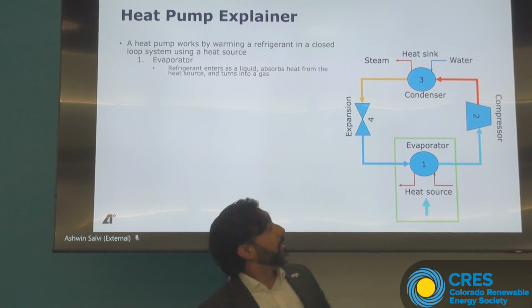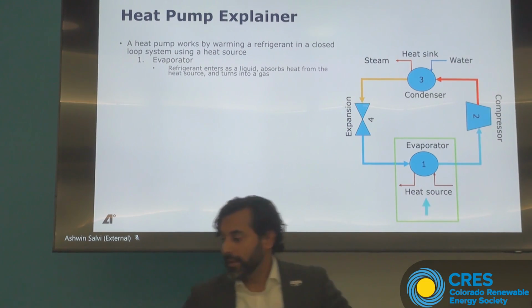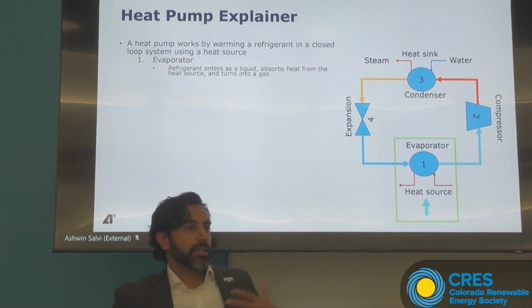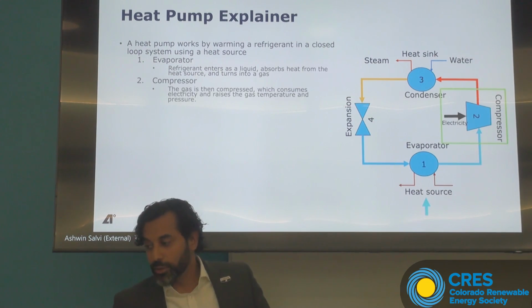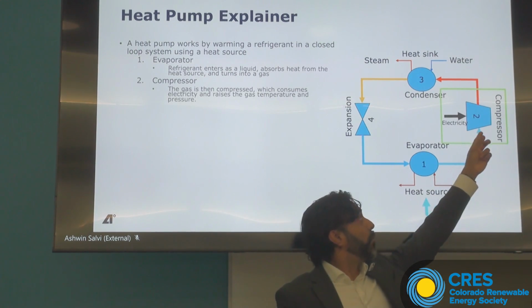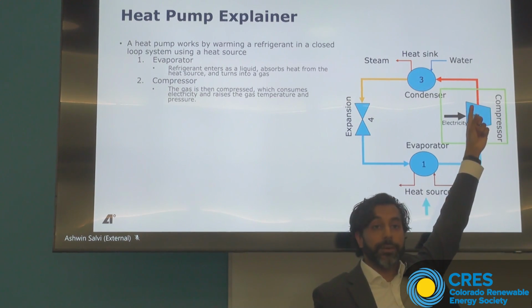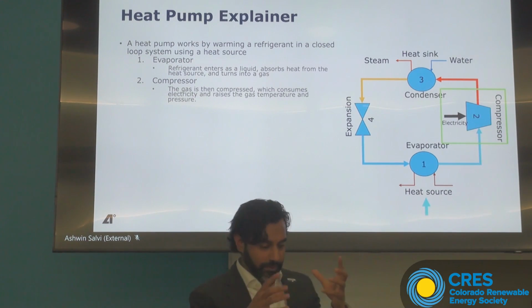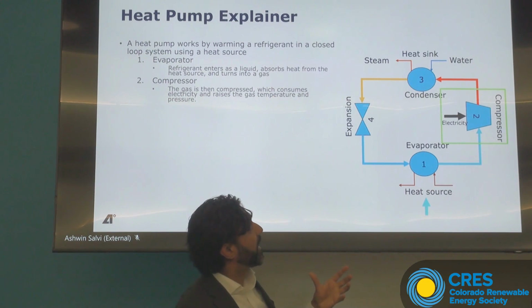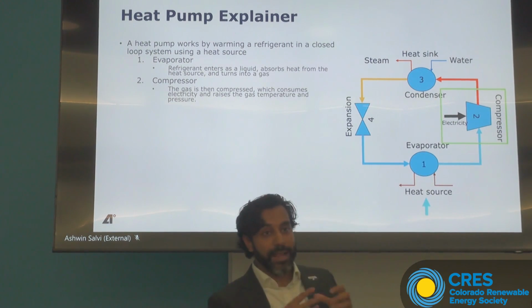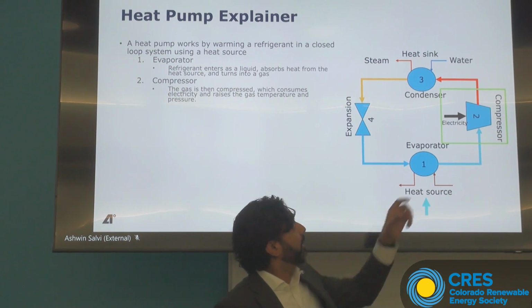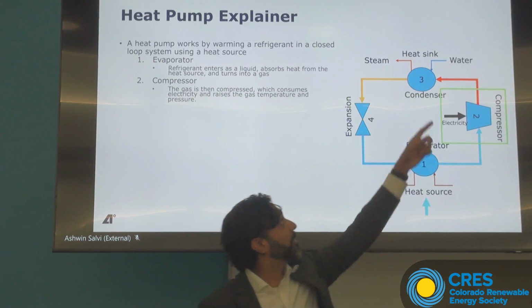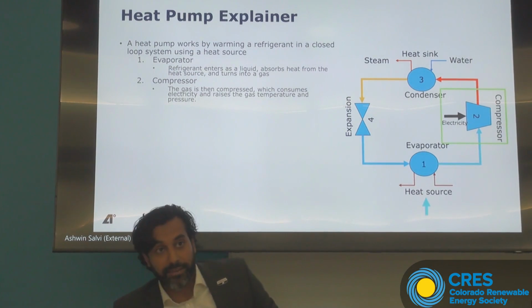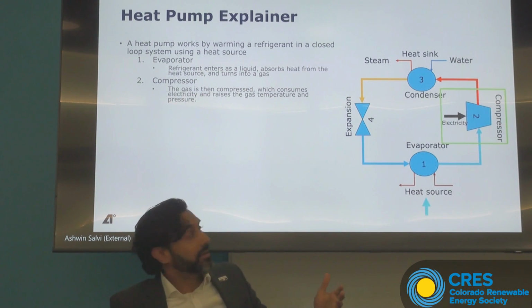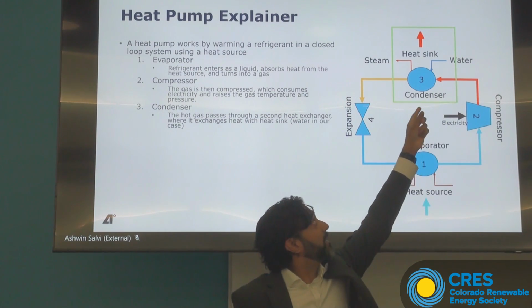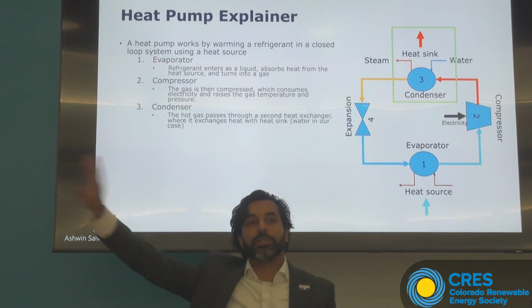That gas is then fed into a compressor, which in our case is driven by electricity - some other folks use heat to drive that compressor - and it takes this gas from one temperature and pressure and compresses it to a higher temperature and pressure. Now that you've got that hot refrigerant gas, you send it through a condenser, transferring that heat into something you want to make hotter. In our case, we're taking water and making it into steam. So we take the work we just put into that gas to make it hot, and transfer that heat out of the refrigerant gas into the water to make steam - and we use that steam to do something else with, right?